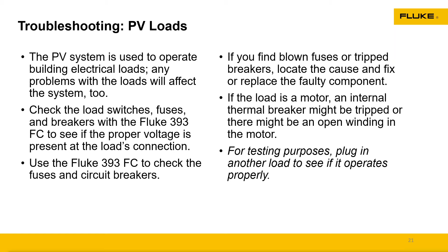If you do find, obviously, a fuse blown or tripped, you've got to figure out what caused it. Being in the HVAC industry for many years, you'd go out to a system and a fuse blew. Why? It's the number one question. You just don't go and replace the fuse. You understand the situation. Why did the fuse even break? The fuse is there for safety. It's there for a reason. So that's where we want to start doing some investigation, running through the system and making sure why that fuse blew and get that corrected. So when we put a new fuse in, we're ready to go again. But there are several things that could be happening just on the load side of it.